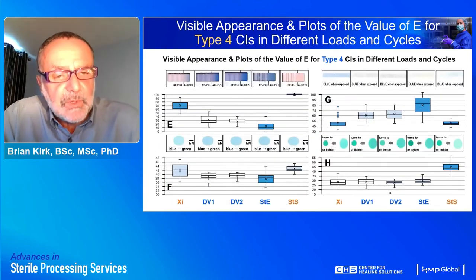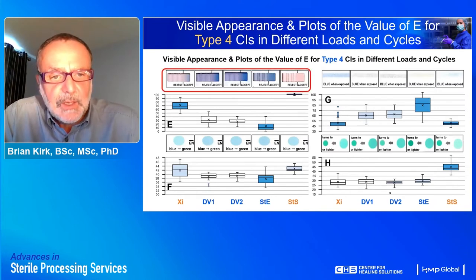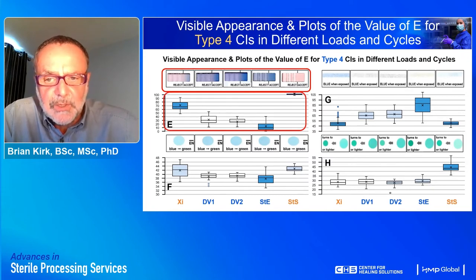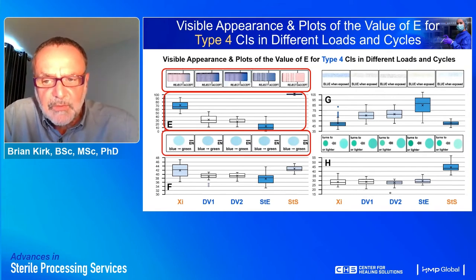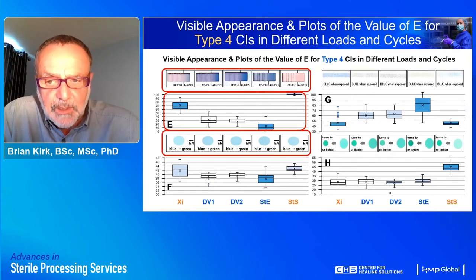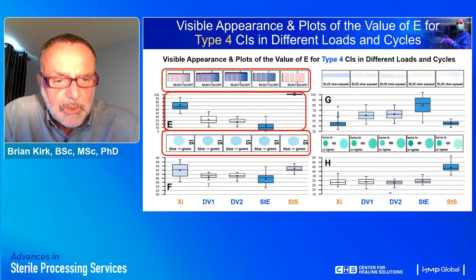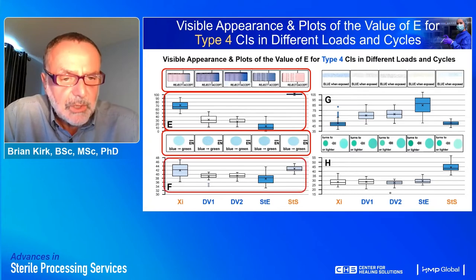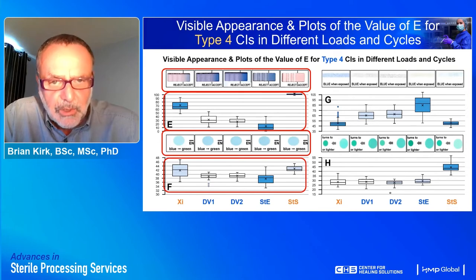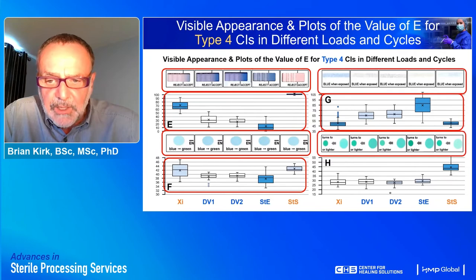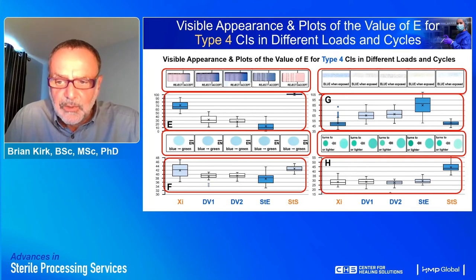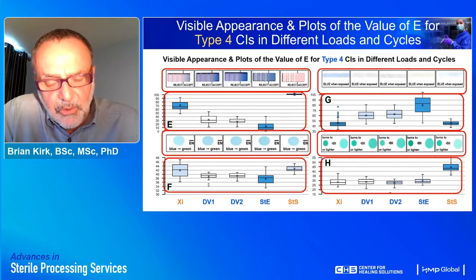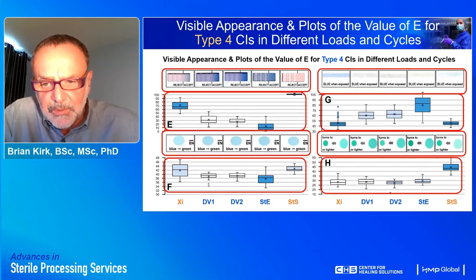Looking at the type 4 CIs in different loads and cycles: products E and G showed observable differences in color between the recommended and not-recommended operating cycles, with measurable statistical differences. Product F showed barely observable differences in color between test conditions and only some statistical differences. Product H showed very slight differences in color between XI and STS and the other three conditions, which were pretty much equivalent to the reference color, so all were interpreted as passes, with some statistical differences observed.